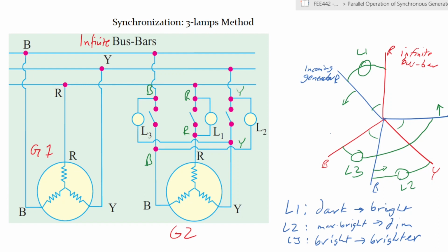When we have achieved synchronization, we will be able to note that the speed of the angle, the movement away from each other between the incoming phase and the infinite busbar, you will have matched so that these will remain stationary. So the idea would be to match them such that there is no phase angle between them. You would want to match them at the point where the red in the incomer is matching the red at the infinite busbar.